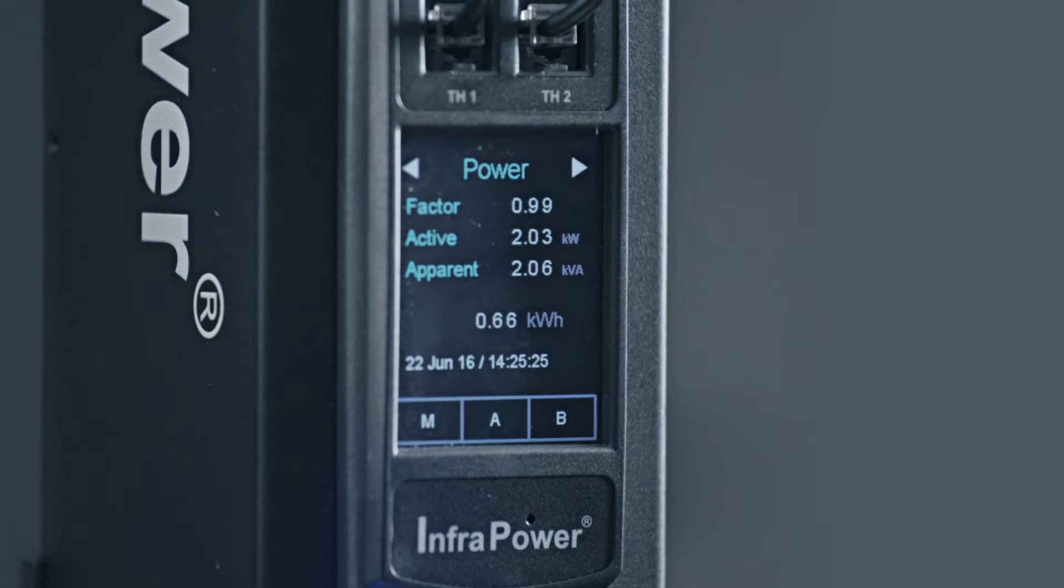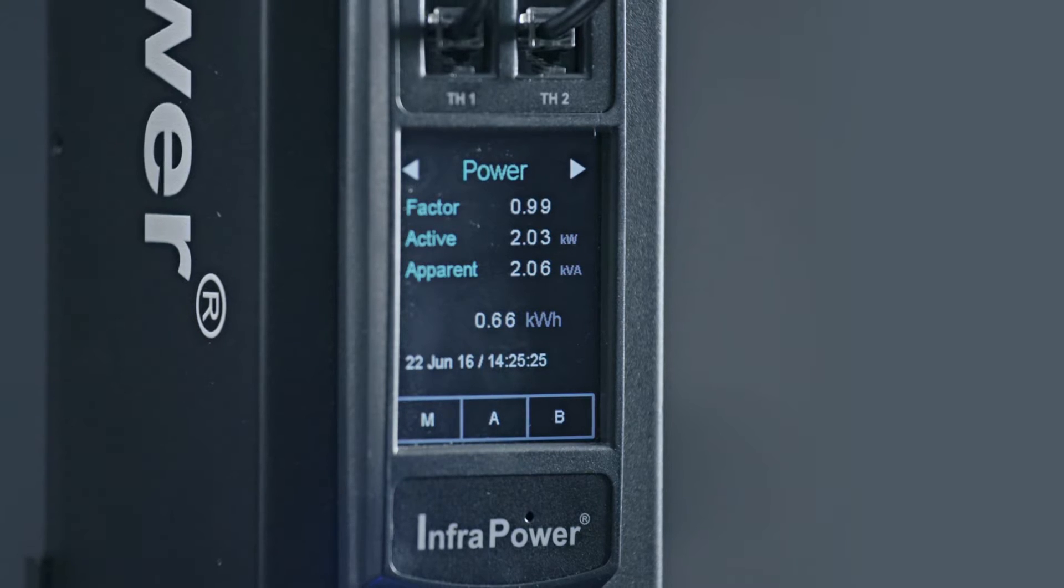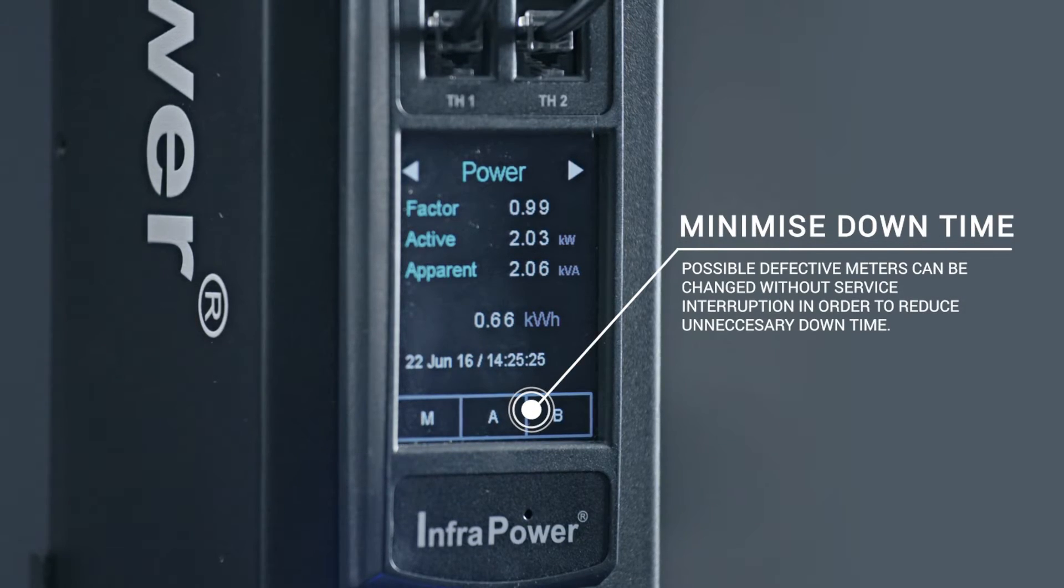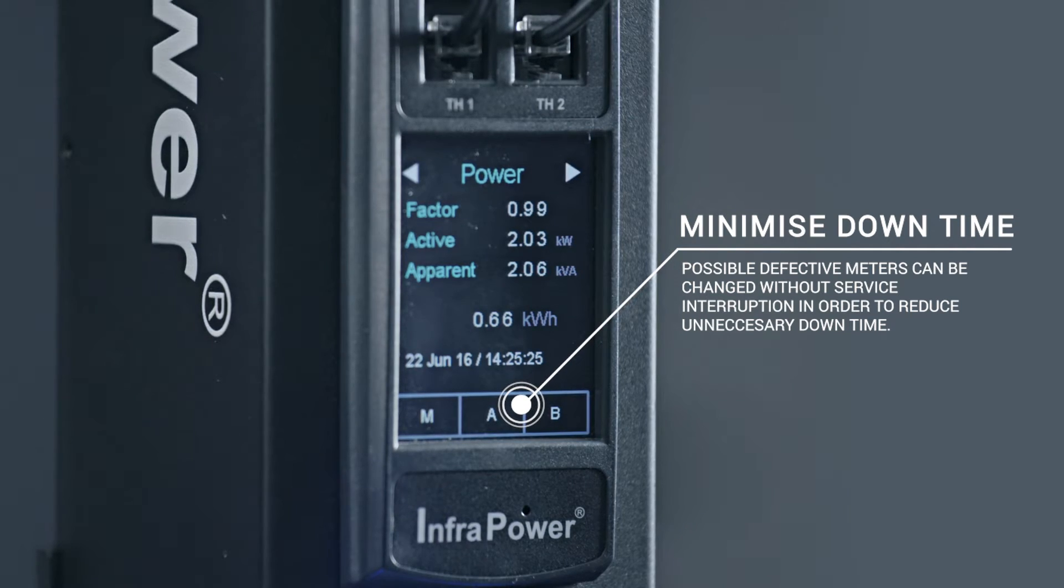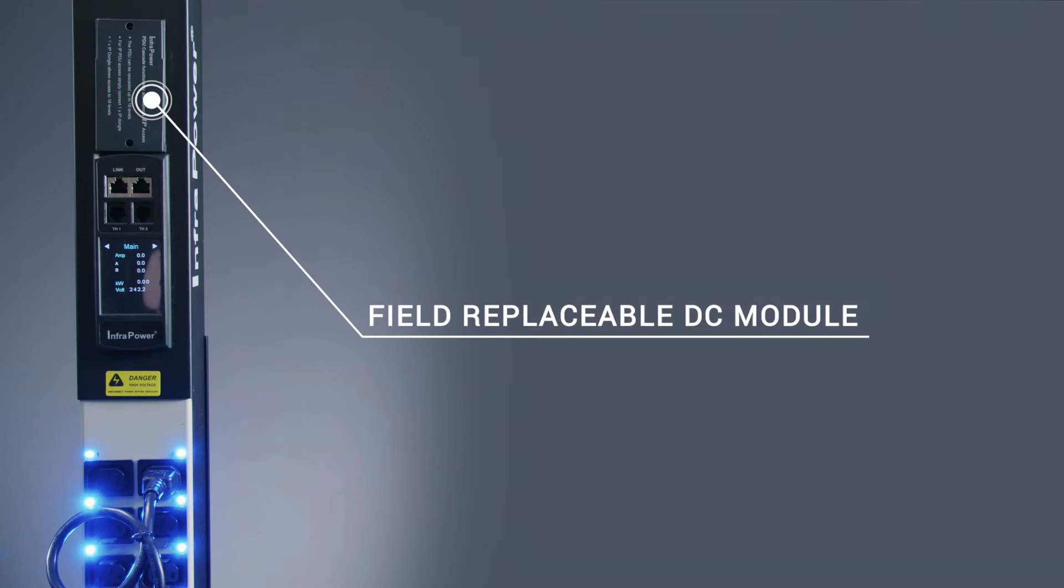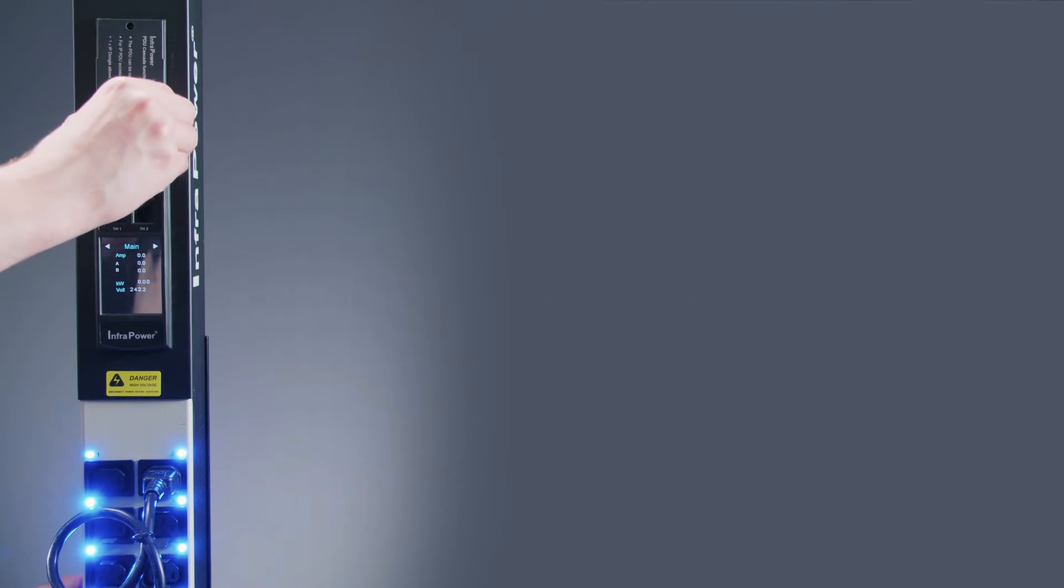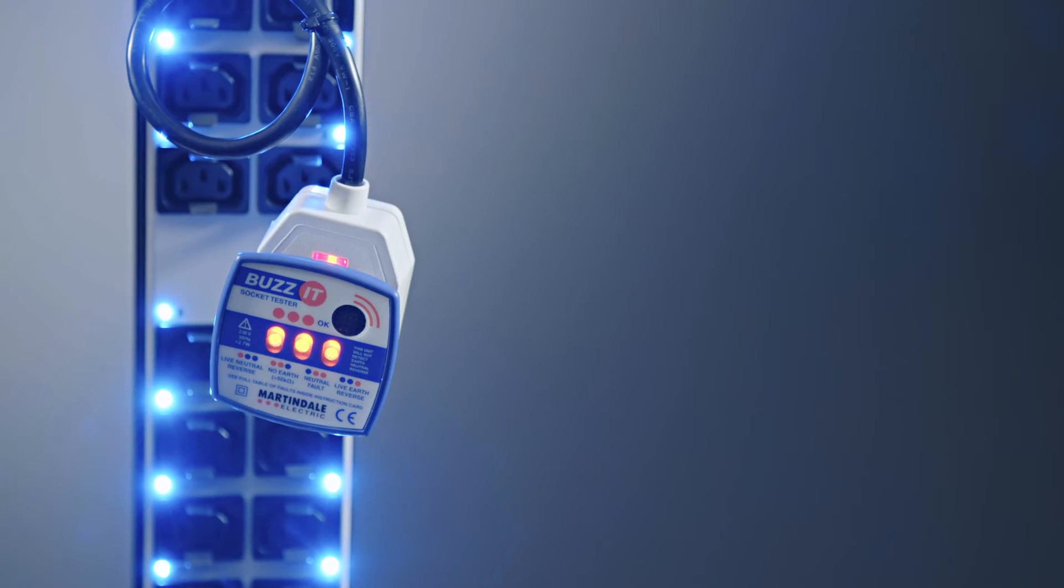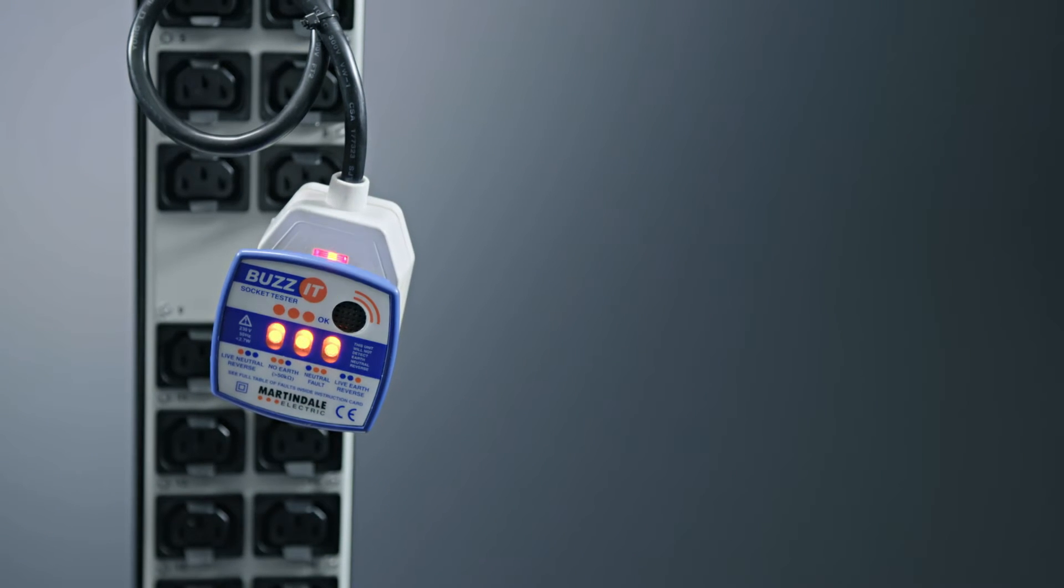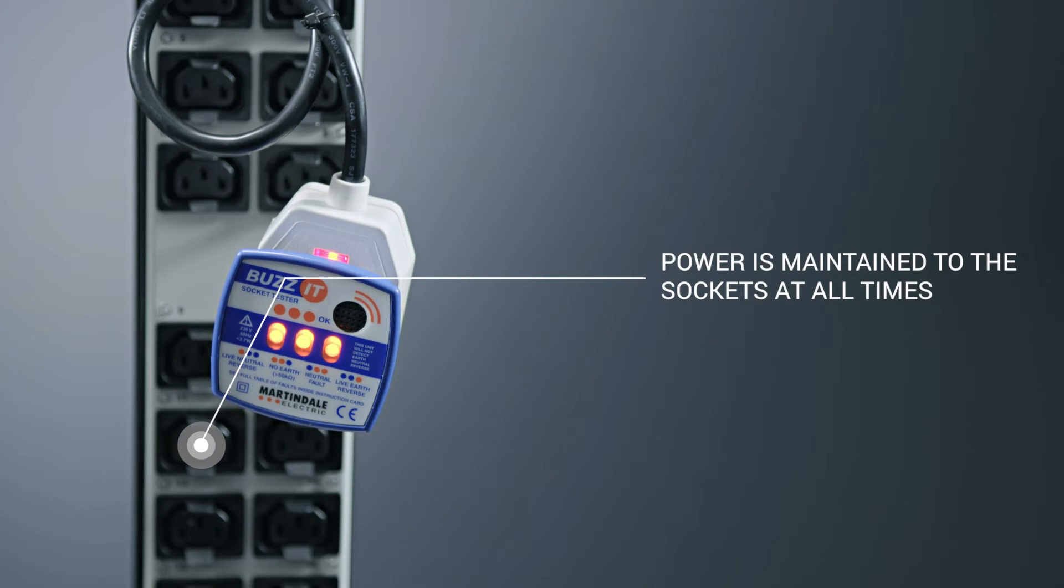The design of the field replaceable display helps eliminate maintenance downtime by simply replacing a possible defective meter without service interruption. The 2.8 inch display is also powered by a hot swappable DC module to avoid unnecessary downtime. Latched relays ensure no disruption of power to critical devices during module replacement maintaining power to the sockets at all times.